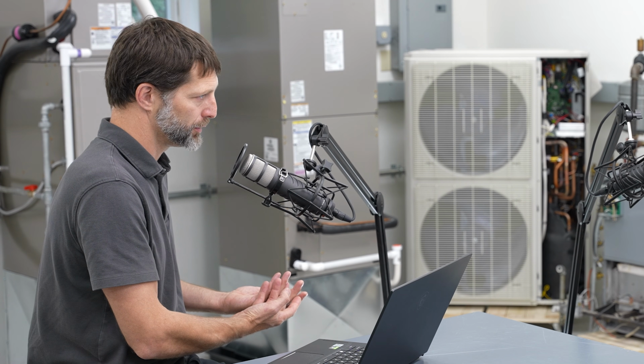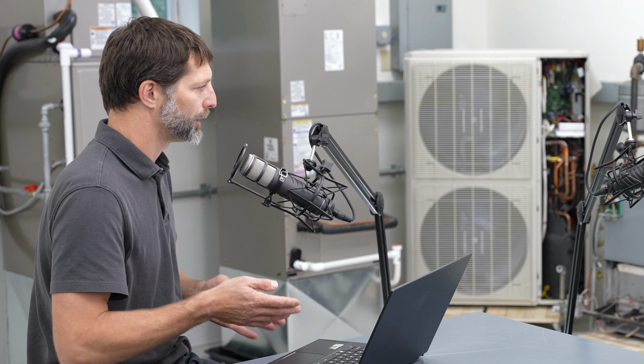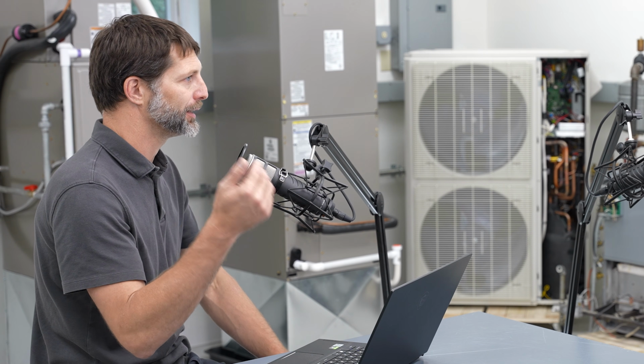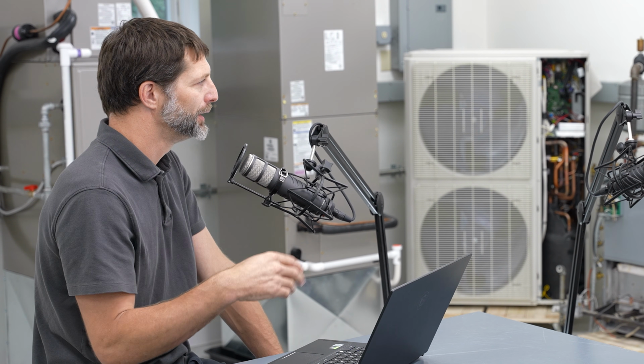When it's controlling something like an ECM motor, it may not have those relays, but you want to know, say if it's a furnace, you want to know the sequence of operation, what the circuit board's supposed to power first in its sequence. You want to know the inputs coming into the board in order to tell it what to do. And that's coming from the thermostat wire and actually from the thermostat. And really, it's from the user setting the thermostat. So it's just a series of steps, and you need to know what to look for first. And it's the inputs first.